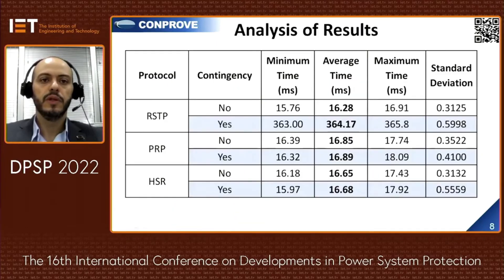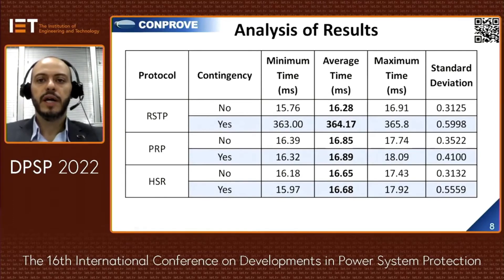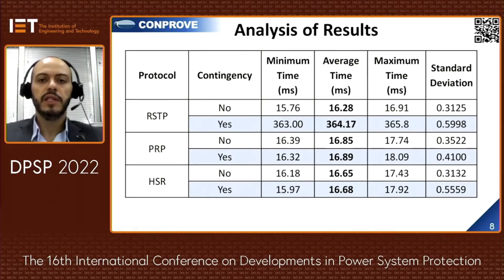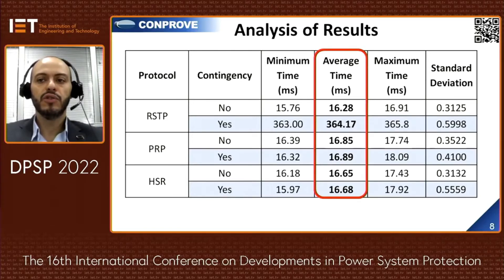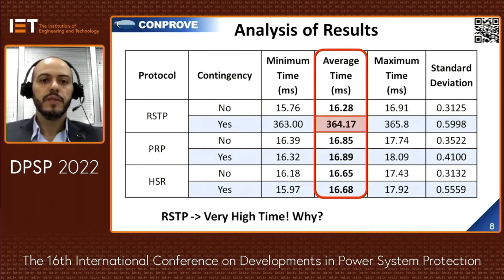In this table, there is a statistical analysis summary of the trip times in each case — protection tests with and without contingencies — comparing the three redundancy protocols. Analyzing the average trip time, it is possible to verify that with PRP and HSR, the average times were very close to each other when link loss occurred. However, with RSTP, the average trip time was very high when the communication path was lost.